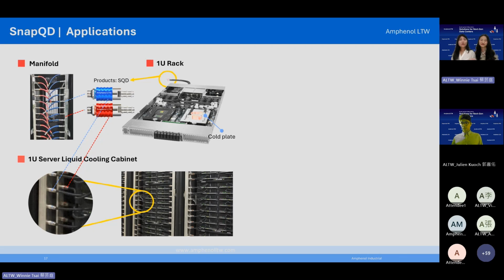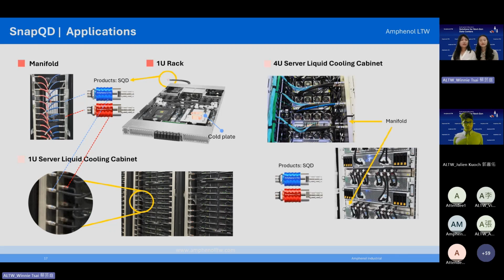While 1U is all about compact design, many data centers also rely on larger server configurations. Here we see a 4U server liquid cooling cabinet. In this configuration, the cooling load is much higher, with more components generating heat, so compared to 1U, the 4U cabinet requires stronger flow performance and even more robust sealing. SnapQD can handle that without any compromise, whether it's small form factor or large scale racks, ensuring consistent cooling efficiency.